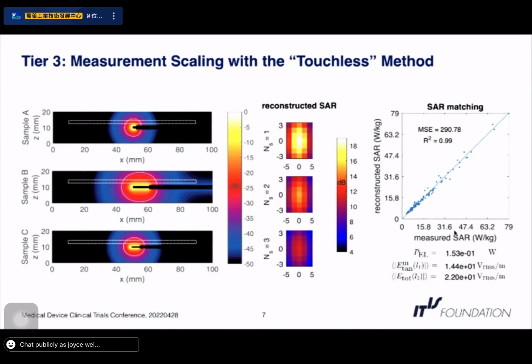In the tier 3, we would use the EM analytics tool that Dr. Goran described earlier to assess the deposited power in vivo. So we determine the worst case, the worst patient, scan position, and coil type with the scan. But this tool needs some inputs that are derived from the test lab and from numerical modeling, which, for example, can be done like this.